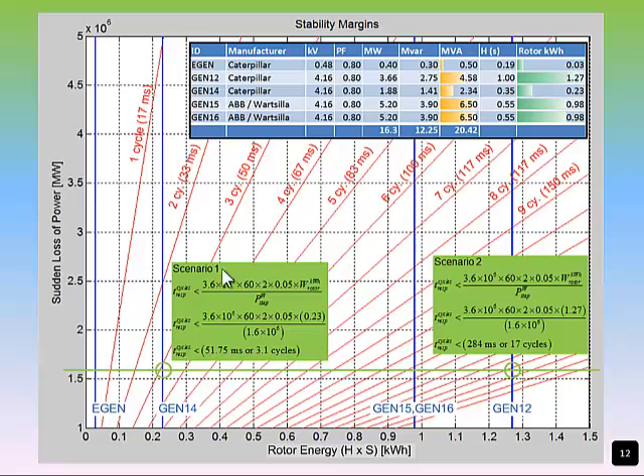Let's take a look at scenario one. Using the calculation shown, the predictions suggest that an energy storage unit must respond in 3.1 cycles to maintain frequency. This is true if using Gen 14, which only has 0.23 kilowatt hours of kinetic energy.